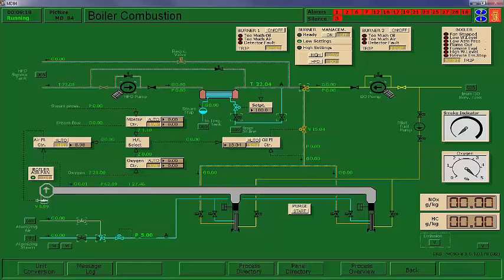Now, one of the advantages we have with this system is that it has a pilot diesel oil pump that will pump oil through this, and then you have a second small burner here that has a spark igniter, and it ignites a small diesel flame that's used to ignite the main fire. Much better system than trying to ignite the main body of the fire with an igniter like you do on a typical oil-fired boiler, say the one that we have on our steam sim.